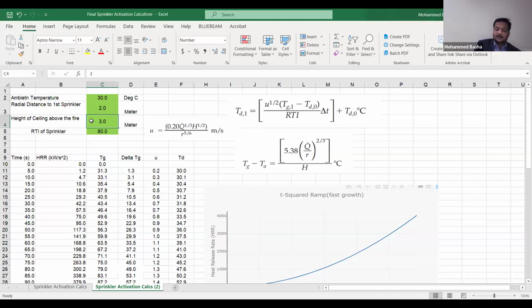I am going to assume 15 meters. What is the RTI of the sprinkler? Response time index, basically. Normally, it's 50 for quick response sprinklers and 80 for standard response sprinklers. Assume I'm going to use a quick response sprinkler.